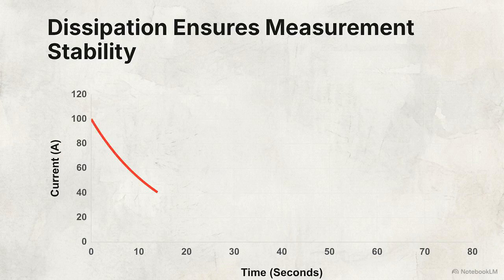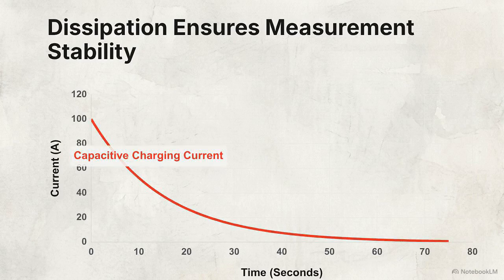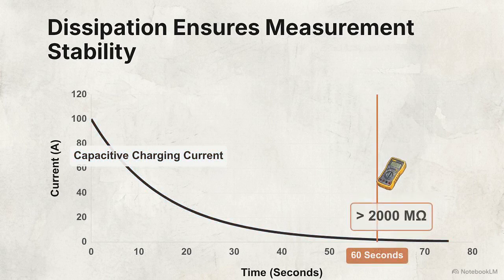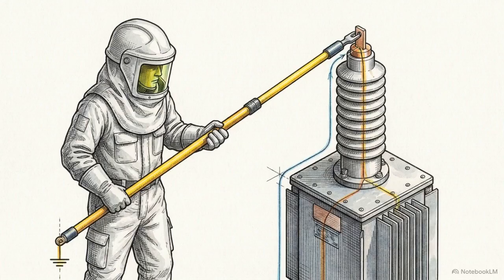For each of these 3 phases, the voltage must be applied for a continuous 60 seconds. This duration ensures the capacitive charging currents dissipate, allowing the resistance measurement to perfectly stabilize. Because DC testing essentially turns the transformer into a large capacitor, leaving any terminal charged is highly dangerous. Complete electrical discharge between each measurement phase is a strict safety mandate.